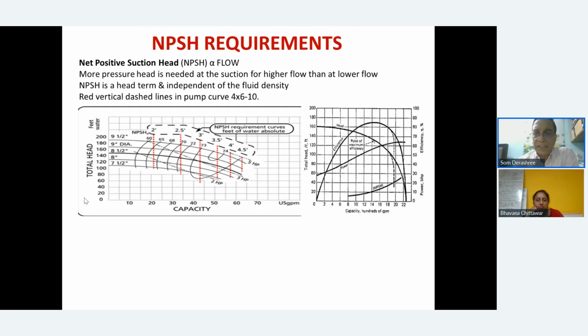Now let's come to what is NPSH required. There are two types. In the US, they follow a system where on the top of the pump curve they have the NPSH requirement, and in other, SI-based systems, you will normally have the NPSH curve on this side. Most of you will be familiar with the NPSH required line at the bottom. So what is given for the pump is the required NPSH, whatever is actually required, not what is available. These are two things which I wanted to share with you.